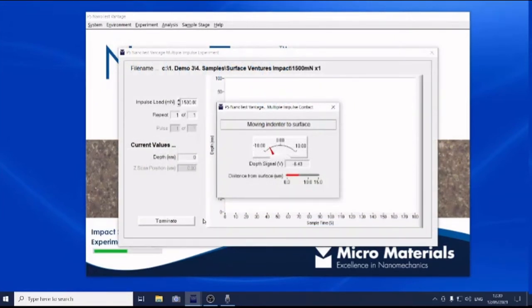Okay, so the instrument is now just placing the indenter on the sample surface to take a reference of where the 0 point is, where the actual starting surface of the sample is. Now it's setting the requested load. So what it's doing is applying this 1.5 newtons of load that we specified. So the probes in contact are just ramping up to 1.5. Okay, and here we go. The impact tests begin.